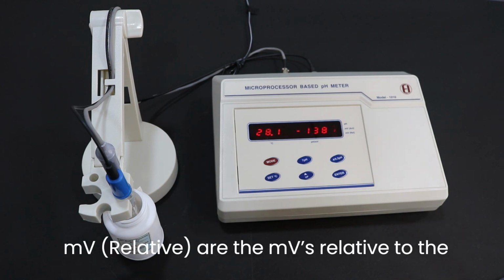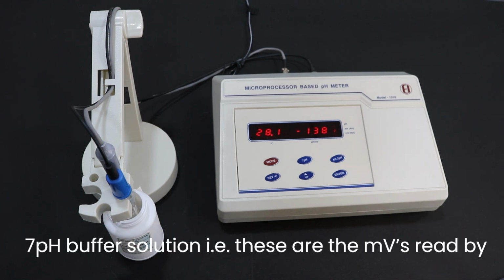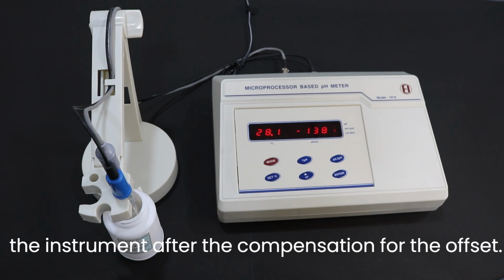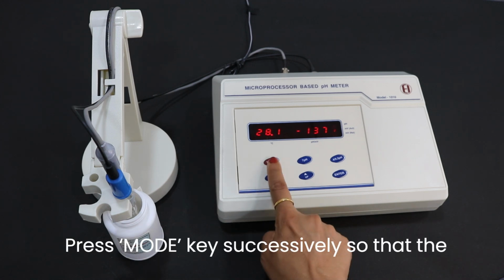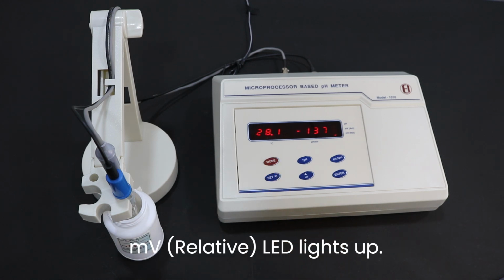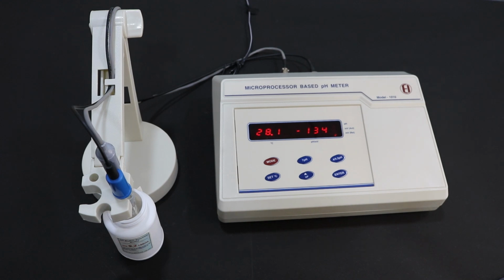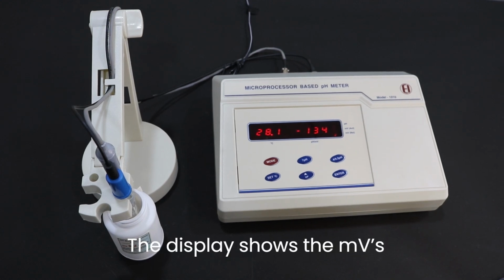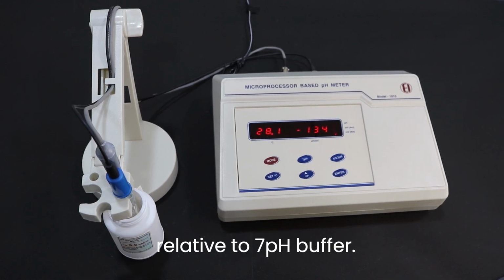MV relative are the MVs relative to the 7 pH buffer solution, that is, these are the MVs read by the instrument after the compensation for the offset. Press mode key successively so that the MV relative LED lights up. The display shows the MVs relative to 7 pH buffer.